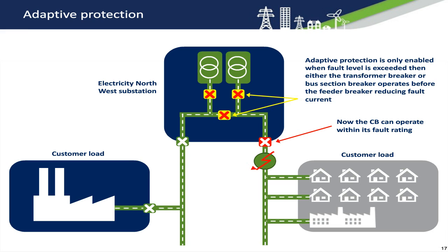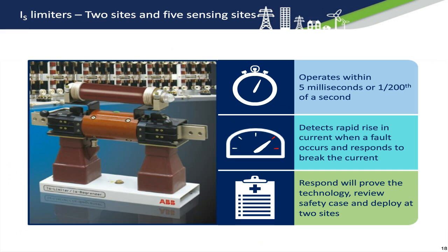The IS limiter, this is our second technique. It is a current limiting fuse. Our standard equipment will normally identify a fault and respond to it within a couple of 100 milliseconds. This may seem fast, but the fault current will have already peaked within this time frame. An IS limiter will operate within 5 milliseconds, or 1/200th of a second, before the fault current reaches its peak.